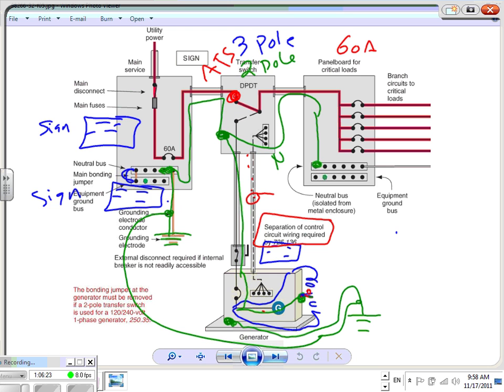Hopefully the generator is warm enough and there's a battery inside the generator. Crank that generator and start. So if you're at home, there's a storm, and a distribution line to your neighborhood is knocked down, your auto transfer switch is sensing it. It sends a signal to the generator, which has a little battery backup for control. It starts the generator through this battery, and it switches the load back to the generator, and your house, your critical loads, are up and running.